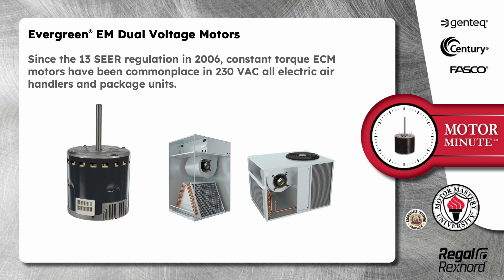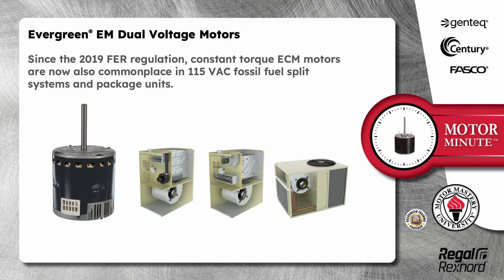Since the 13 SEER regulation in 2006, constant torque ECM motors have been commonplace in 230 volt all-electric air handlers and package units. Since the 2019 FER regulation, constant torque ECM motors are now also commonplace in 115 volt fossil fuel split systems and package units.